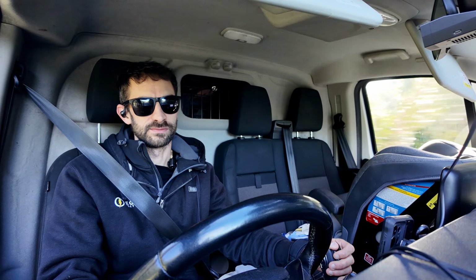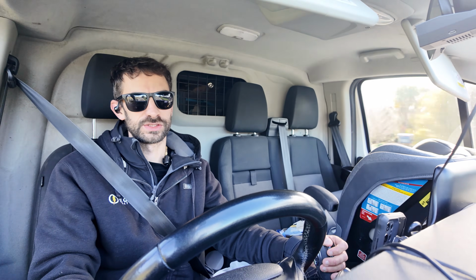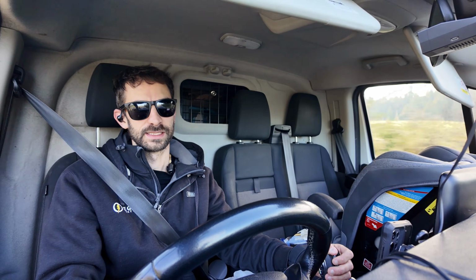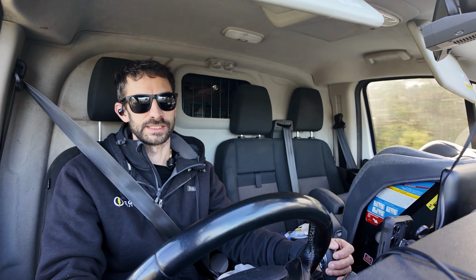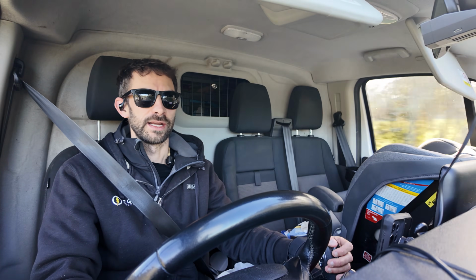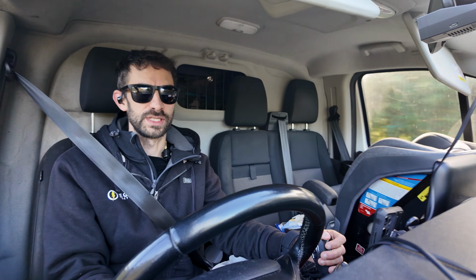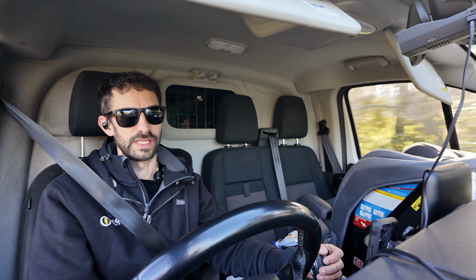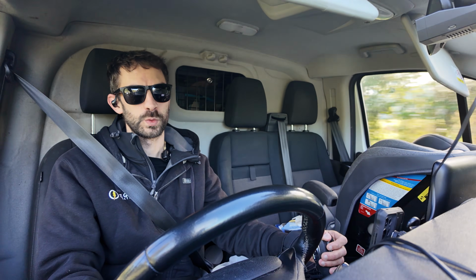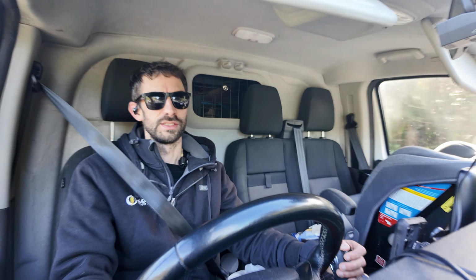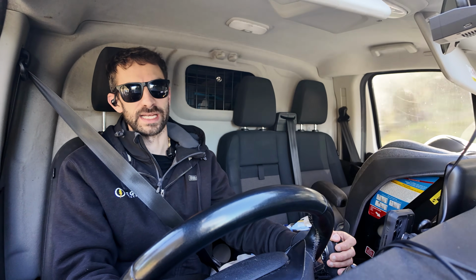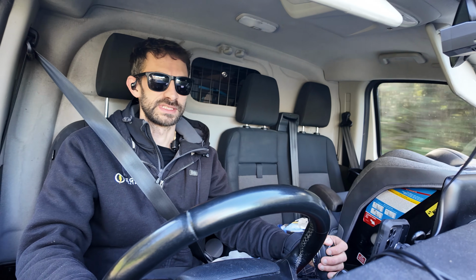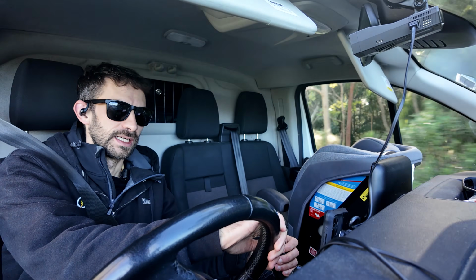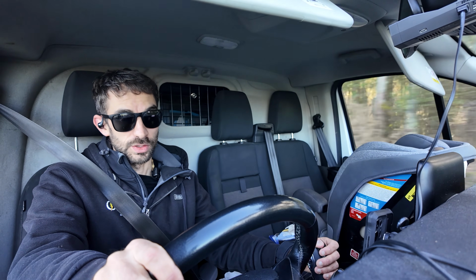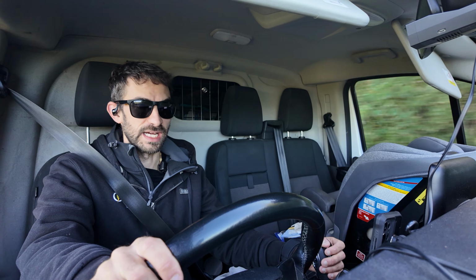So there is an idea that the high resistance that the earth electrode gets, say 100 ohms in a bad case, is not enough to trigger overcurrent protection, but it is enough to trigger RCD protection. But this is where we could talk about another risk that the earth electrodes bring, which is that they create a fault current between a person back to the conductor, because you've now connected the neutral back to the soil around your house. So if you're standing on wet ground in bare feet near the earth rod, you have a really good connection between you and the transformer. And if you then touch a voltage source, you can get a really bad shock and it could be fatal.